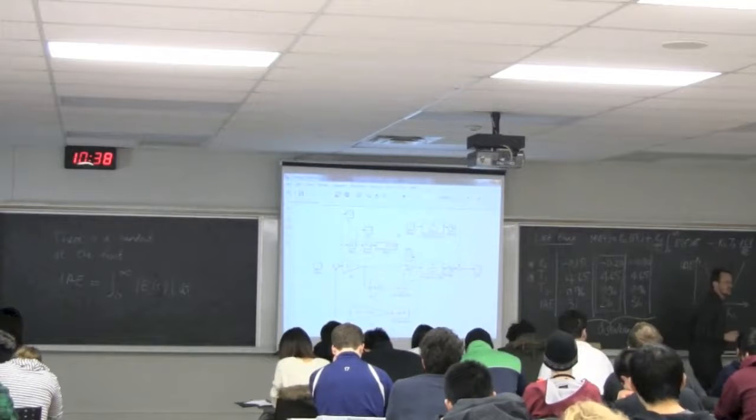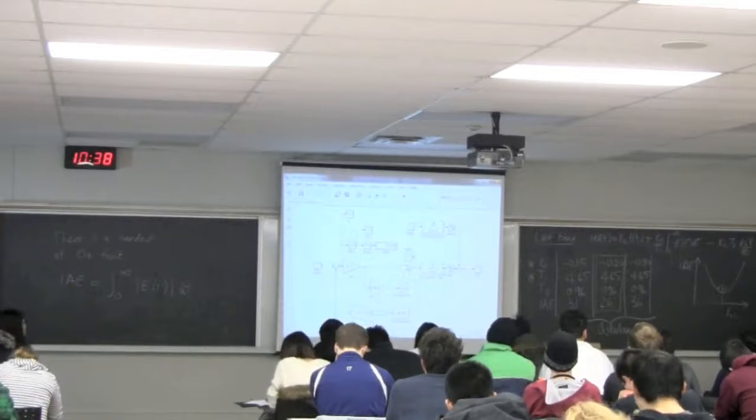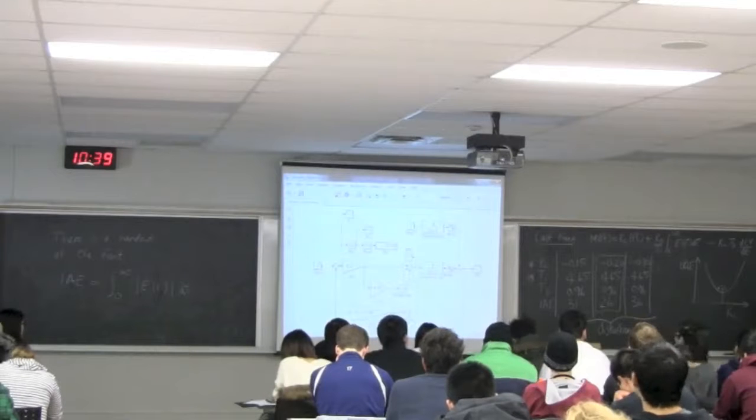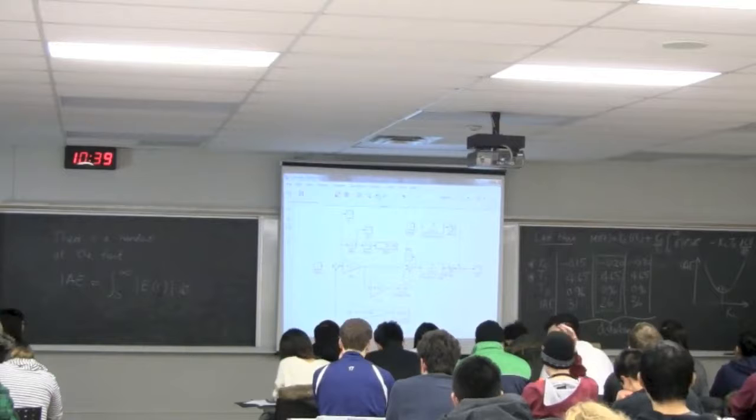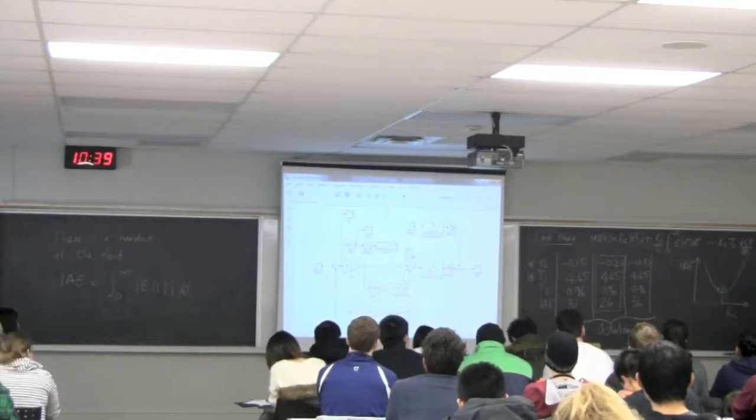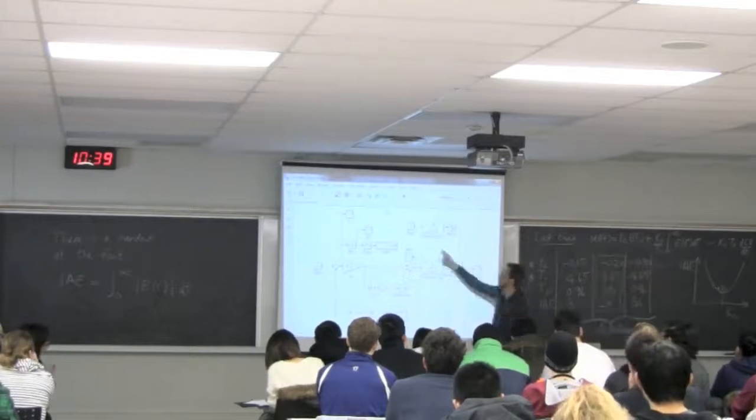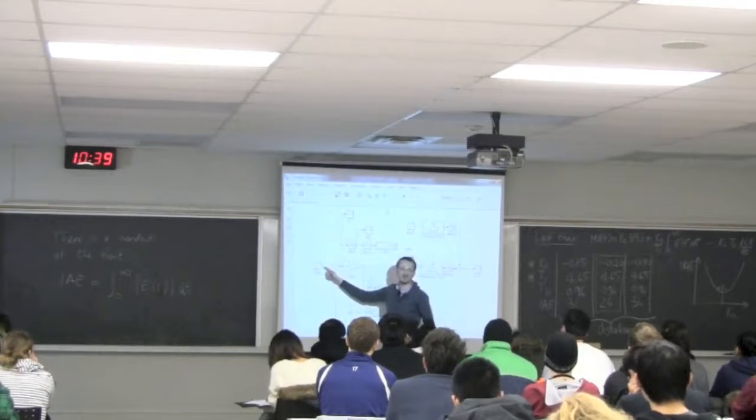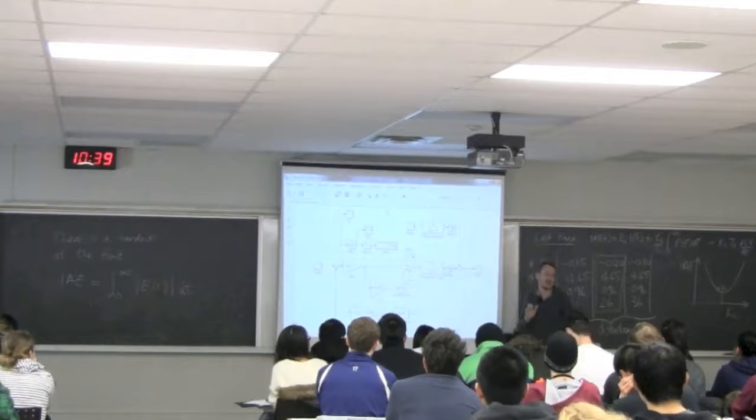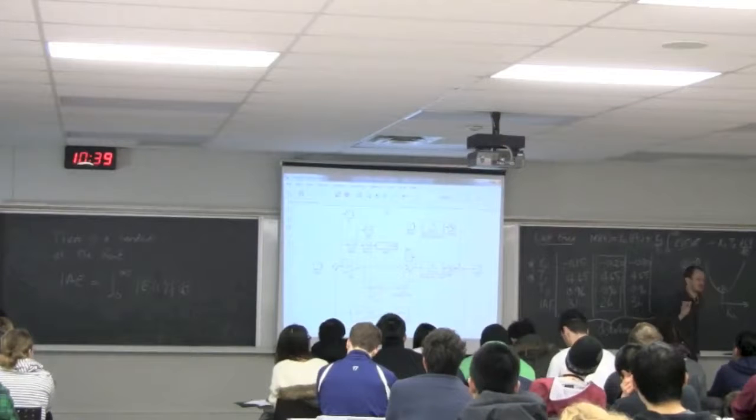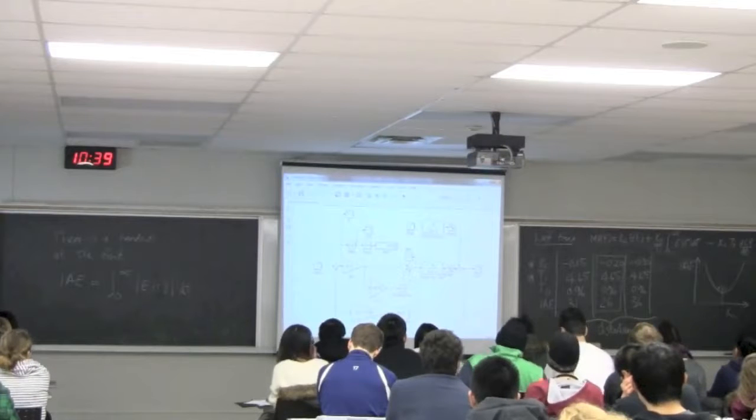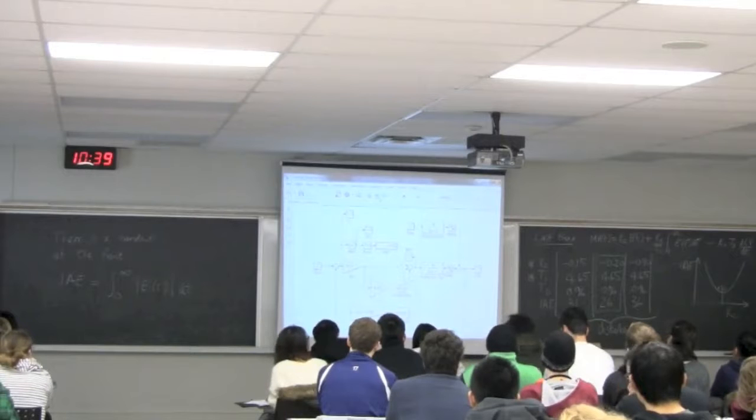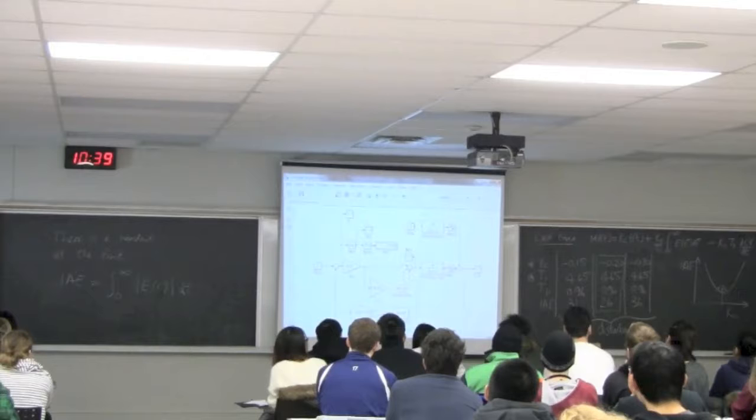So this is fine-tuning. The table will get you into a ballpark region that you can fine-tune. The table will get you somewhere close by. You can explore around to see where the action really is for your process. But this was for disturbances. This was a simulation where I was only changing the disturbance. Notice here the set point. I've actually removed that wire. That signal coming in is zero, so we're not making set point changes.